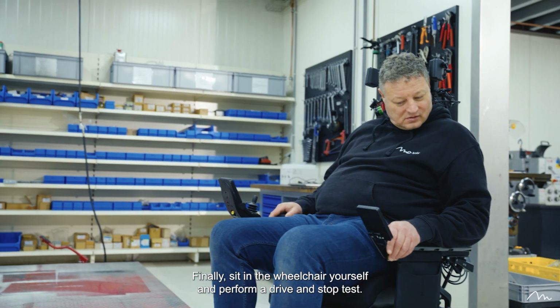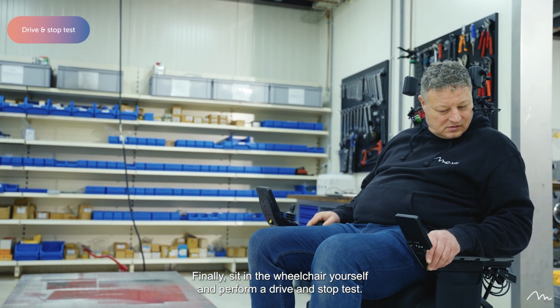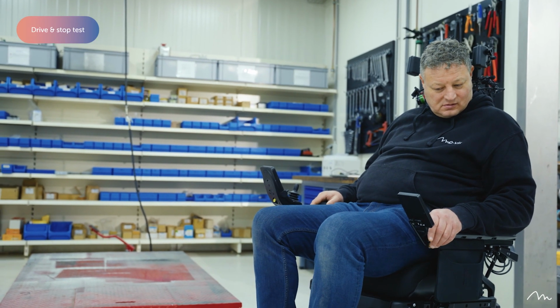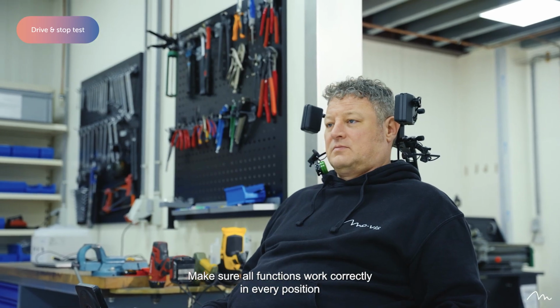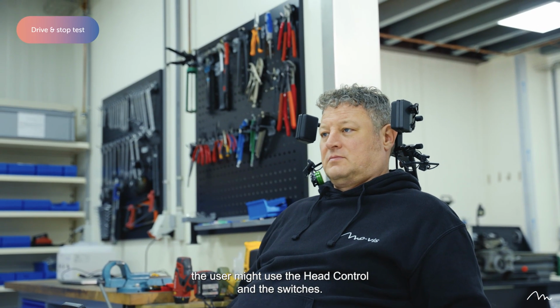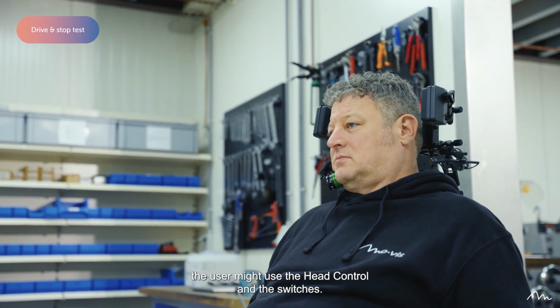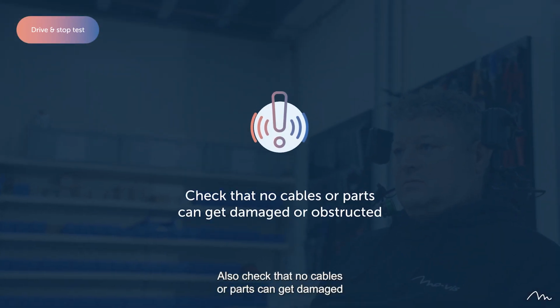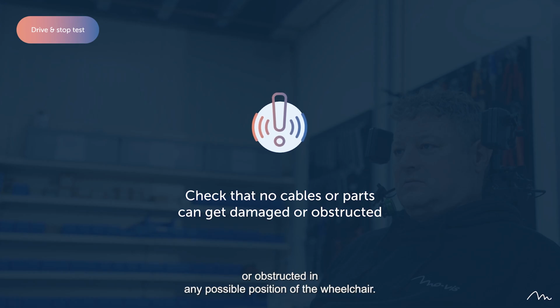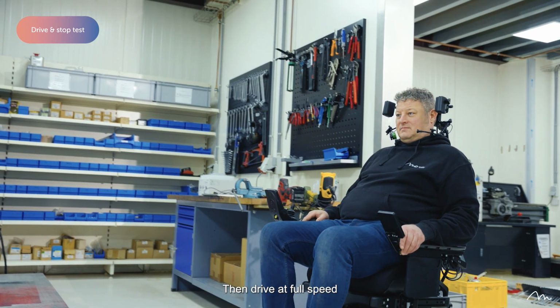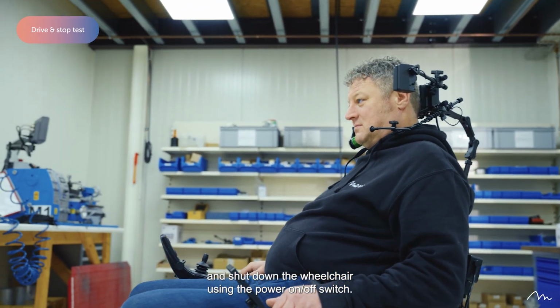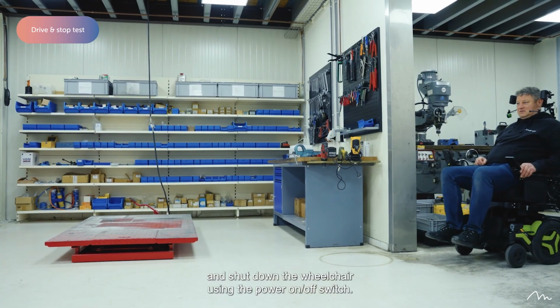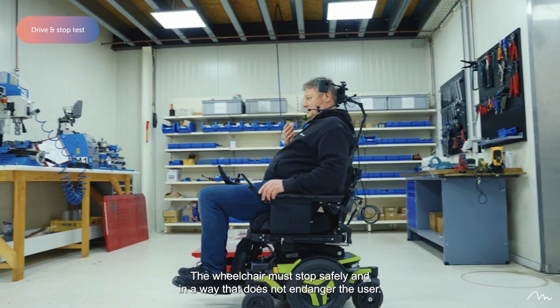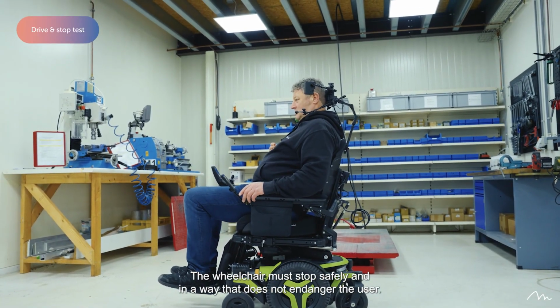Finally, sit in the wheelchair yourself and perform a drive and stop test. Make sure all functions work correctly in every position the user might use the head control and the switches. Also check that no cables or parts can get damaged or obstructed in any possible position of the wheelchair. Then drive at full speed and shut down the wheelchair using the power on/off switch. The wheelchair must stop safely and in a way that does not endanger the user.